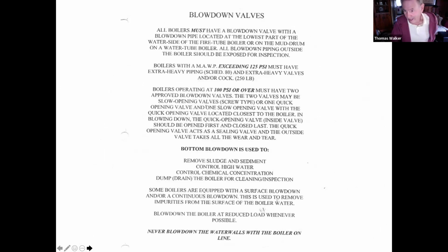We talked about blowdown valves. You've got to have a way to drain the boiler, let water out of it. The blowdown pipe should be attached to the lowest point on the water side of the boiler. That pipe should be exposed, which means it shouldn't be insulated, because we would like to know if it has a hole in it or a leak. Again, the big question is, when do I need more than one blowdown valve? It's on any boiler that operates at 100 PSI or over. You can have one quick opening valve and one slow opening valve to make it easier for you to blow down the boiler.